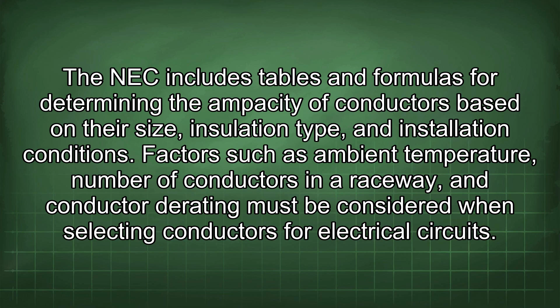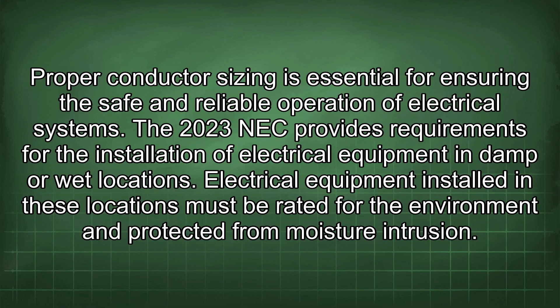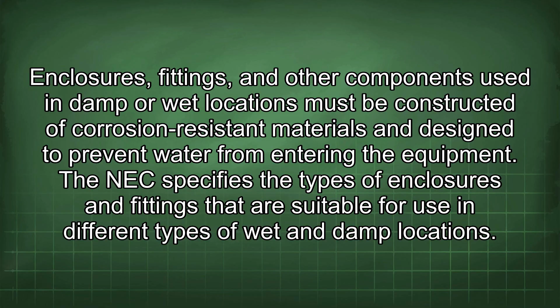The 2023 NEC provides requirements for the installation of electrical equipment in damp or wet locations. Electrical equipment installed in these locations must be rated for the environment and protected from moisture intrusion. Enclosures, fittings, and other components used in damp or wet locations must be constructed of corrosion-resistant materials and designed to prevent water from entering the equipment. The NEC specifies the types of enclosures and fittings that are suitable for use in different types of wet and damp locations. Proper installation of electrical equipment in these locations is essential for preventing electrical shock hazards and equipment damage.